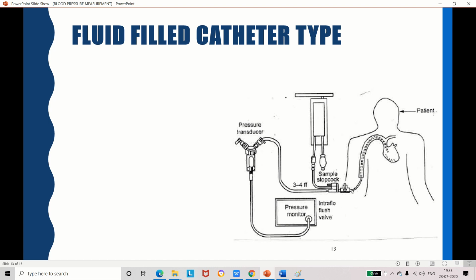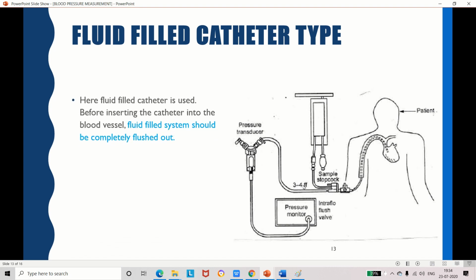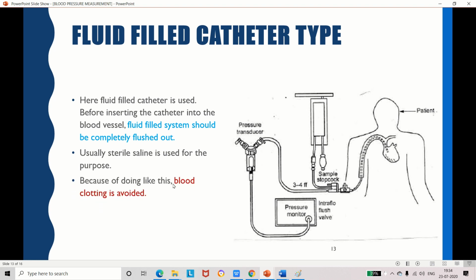Now we are fixing this catheter into the tissue, into the internal organ, fixing the catheter tip. Before measuring, we have to flush out this tube using sterile saline so that the blood vessel can be avoided from clotting. So the fluid filled system should be completely flushed out using sterile saline, and by using this flushing mechanism, blood clotting can be avoided.